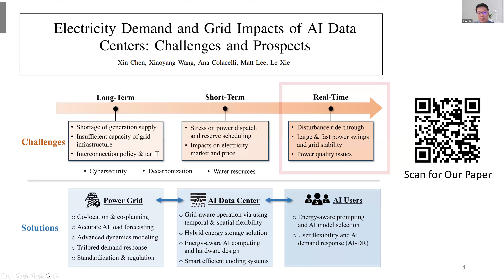The first key challenge is the disturbance ride-through issue, because data centers are power electronics based, which are very sensitive to power grid side disturbances like voltage sag, which can lead to tripping of the entire data center facility.